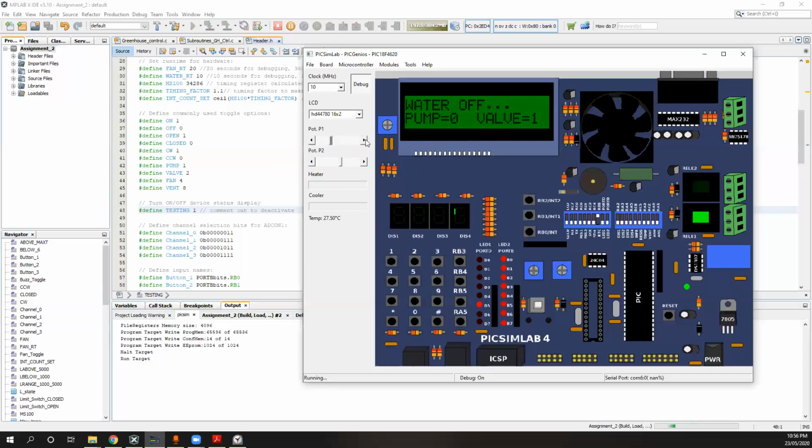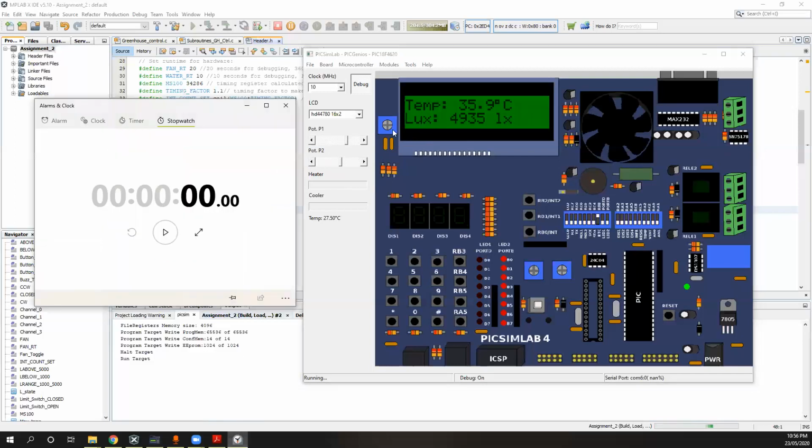The next one for the sprinklers is it's triggered when the temperature rises through 36 degrees, okay? So we'll get up right on the borderline of 36 degrees, and then we'll get it going from there. I might time this one so you can see what the timing's like. When that goes over 36 degrees, the sprinkler should turn on for 10 seconds. All right, ready? All right, we're timing that.